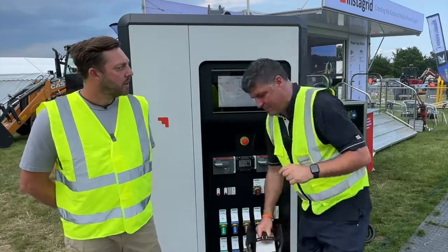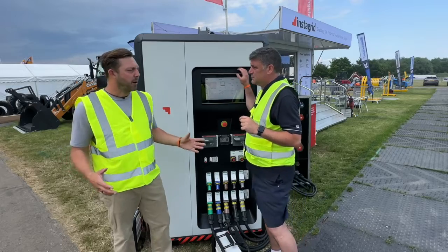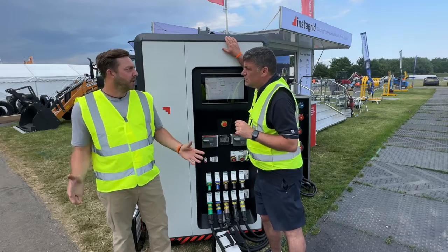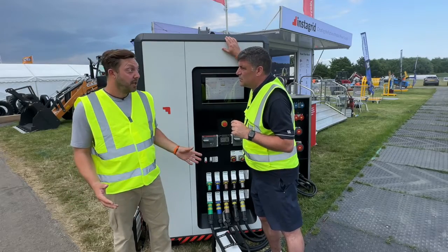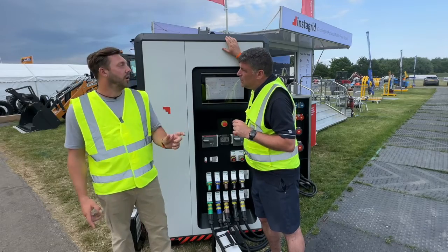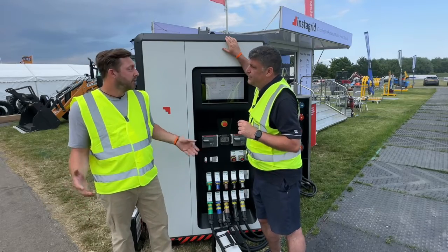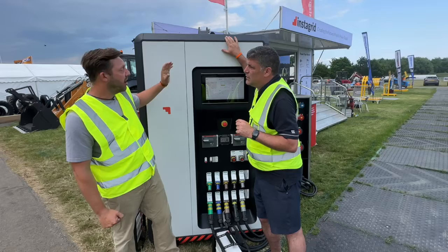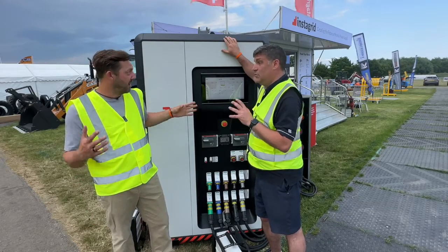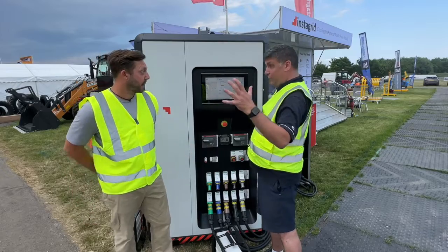InstaGrid is fundamentally built on a completely new platform. We use micro inverters as opposed to one centralized big inverter, and that brings a bunch of benefits. The reason we can get so small is that our inverters are way smaller than a big centralized inverter. This machine is about a third of the size and weight of comparable machines that have this kind of performance.